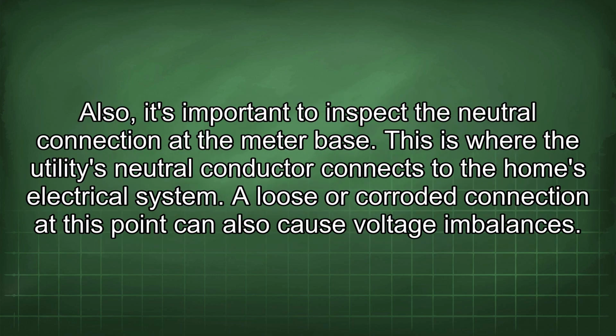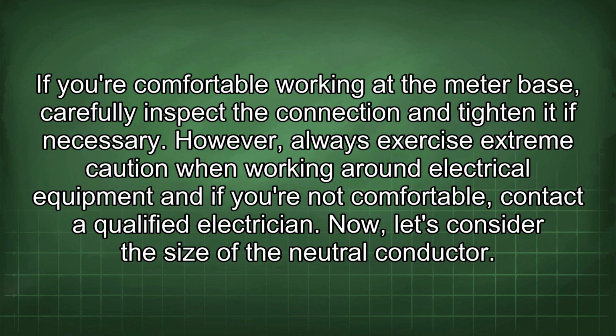Also, it's important to inspect the neutral connection at the meter base. This is where the utility's neutral conductor connects to the home's electrical system. A loose or corroded connection at this point can also cause voltage imbalances. If you are comfortable working at the meter base, carefully inspect the connection and tighten it if necessary. However, always exercise extreme caution when working around electrical equipment, and if you're not comfortable, contact a qualified electrician.